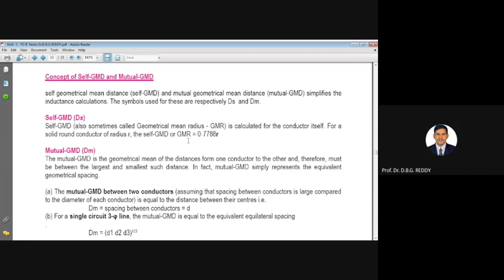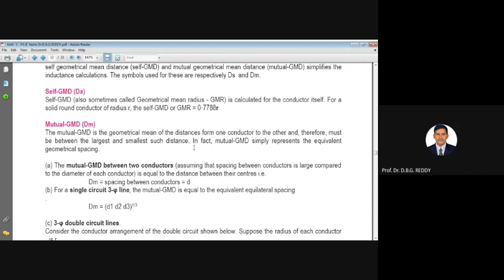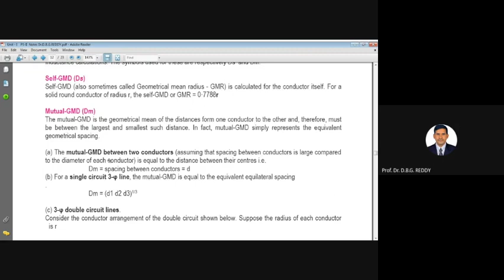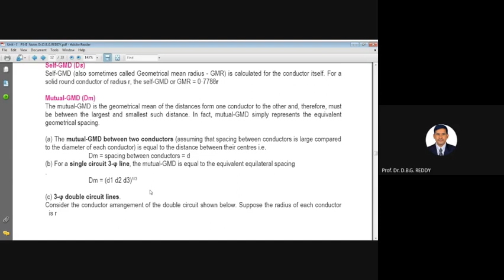So self GMD, DS, is also sometimes called the geometrical mean radius. It is calculated for the conductor itself. For a solid round conductor of radius R, self GMD is equal to 0.7788 R. And mutual GMD is the geometrical mean distance from one conductor to the other. Mutual means one conductor to the other. Mutual meaning is clear. Therefore, there must be a largest and smallest such distance. In fact, mutual GMD simply represents the equivalent geometrical spacing. Now mutual GMD is equal to the cube root of D1, D2, D3 only if the distances are unequal. If it is an equilateral distance, DM is equal to D only.